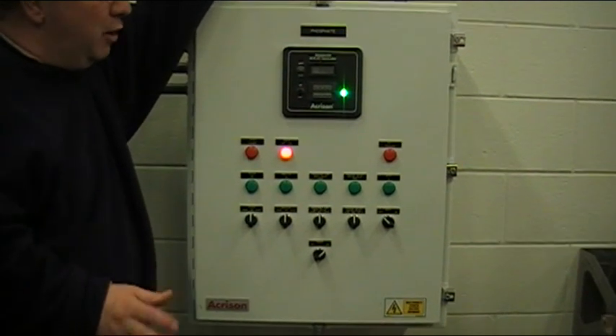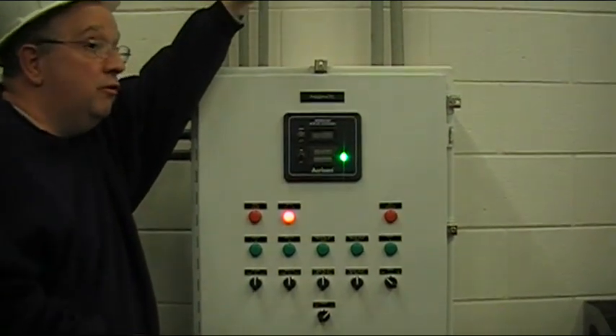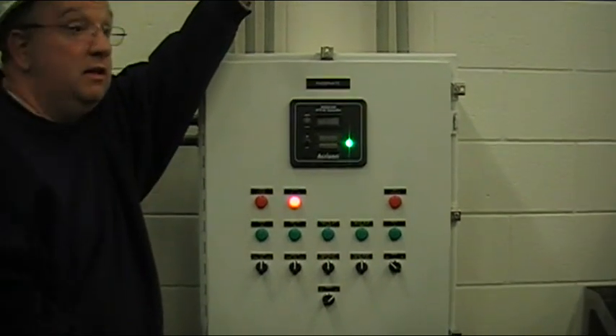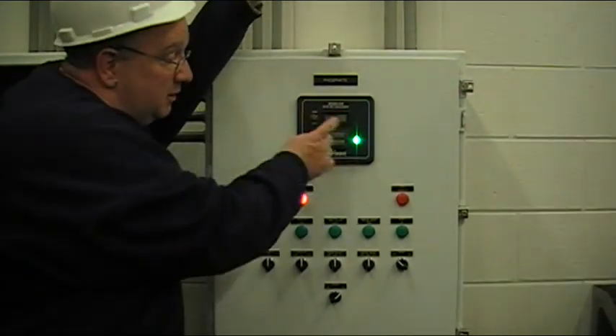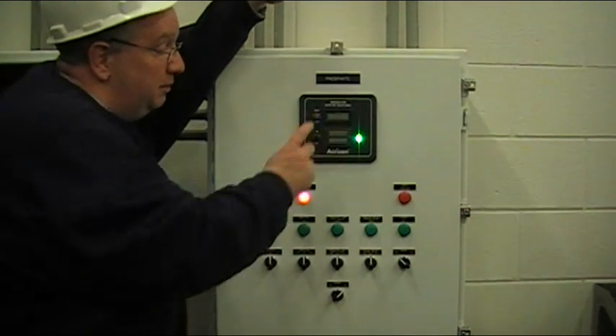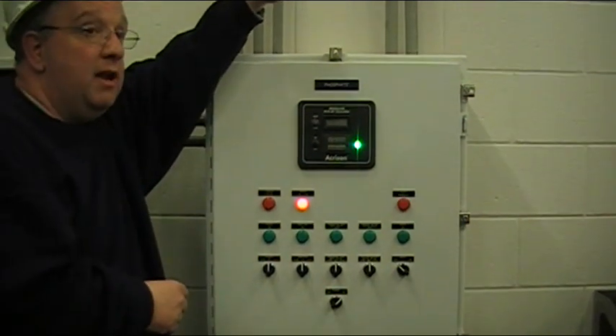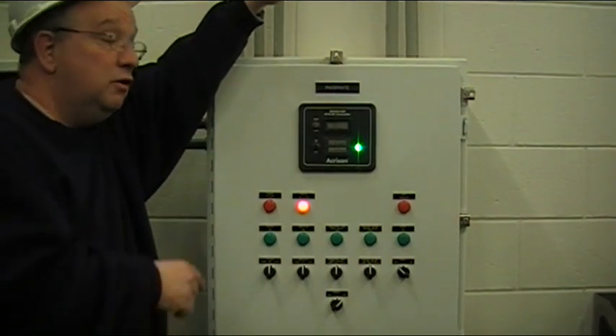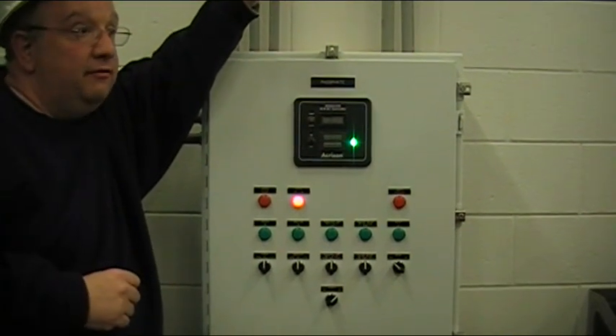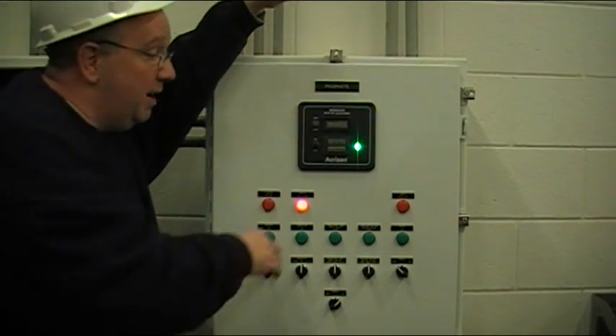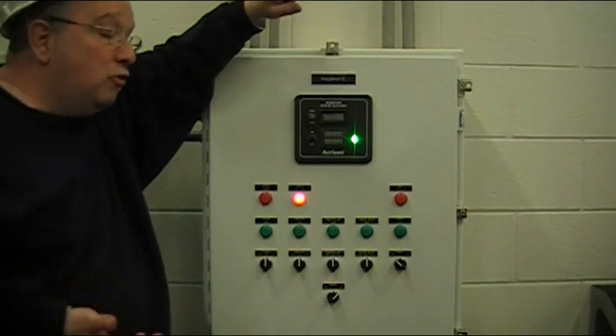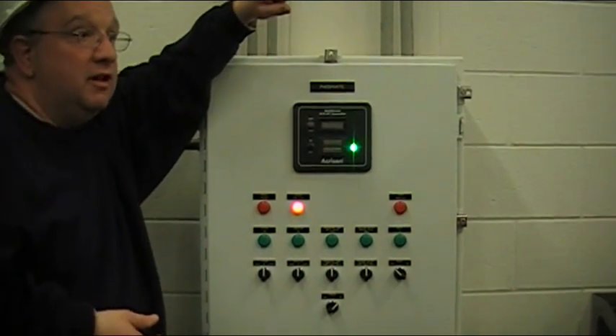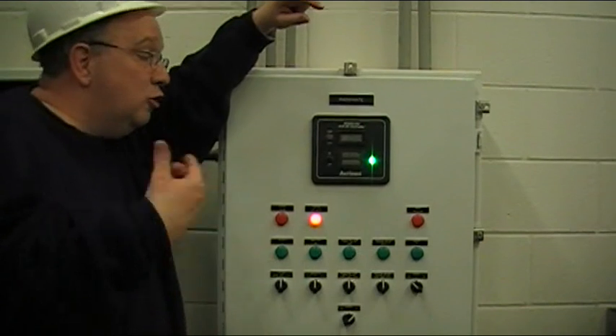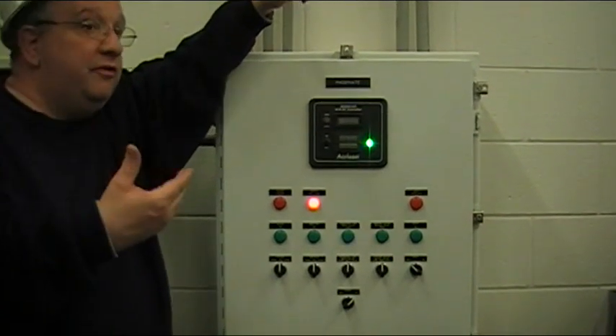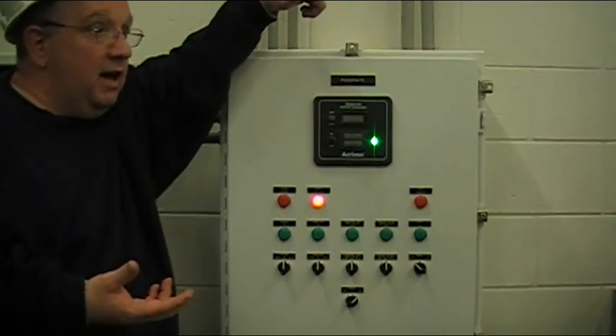Otherwise, if the motor binds up, or you leave product in it for a long time and it binds, this light will start blinking. When the light is blinking, it means the unit is drawing more amperage, it's going into current limit. You'll get an alarm back on the SCADA saying feeder alarm. But if you come out and see it blinking, most commonly it's something stuck inside the feeder, or something mechanically wrong with the feeder, motor, gearbox, or similar.